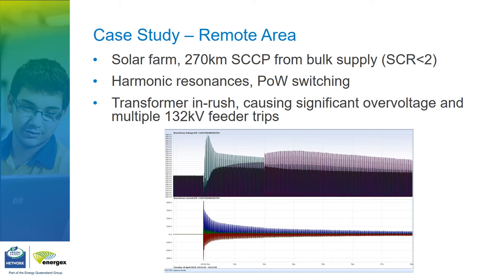And for that particular area, there have been known harmonic resonances on this network for decades. And that's been appropriately managed by our processes. However, it's not until we performed detailed studies that we were able to determine the real risk to the system of having a solar farm connected. And that's important to highlight, because the connection process we see is an iterative process, and it's really there to uncover the potential issues relevant to the connection. And sometimes those issues are not obvious.